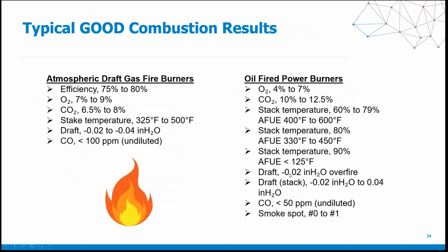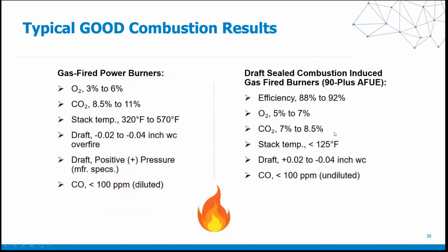50 ppm undiluted. And when we talk about oil systems, it's very, very important that before you perform a combustion analysis on an oil-fired piece of equipment, you do a smoke test. Because you don't want to put your probe into a sooted up or a very dirty system, because you have the propensity to pull some of that sootiness into the analyzer itself. And that will inhibit the analyzer's performance going forward and shorten its lifespan and also shorten the lifespan of your sensors. So it's very important that you perform a proper smoke test. Know that you have clean working conditions before you go ahead and start your combustion analysis.